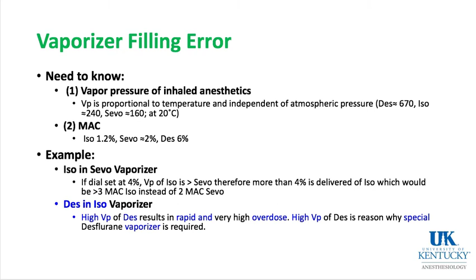If you happen to put DES, if you could, in an isoflurane vaporizer, when you turned on the isoflurane vaporizer, there would be a high delivery of the gas, because the high vapor pressure of desflurane results in rapid and very high overdose. We need that special vaporizer that desflurane is delivered with that keeps it at 2 atmospheres and 39 degrees so that we can deliver it at a known concentration.